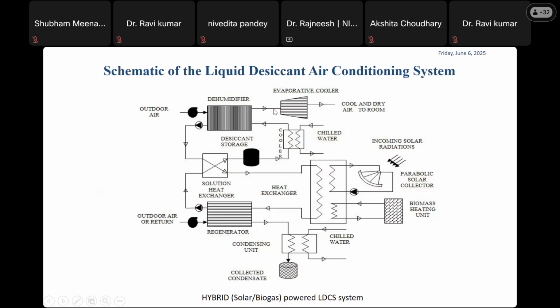And as we discussed with the help of psychrometry, the moisture content is also to be increased a little bit up to the comfort conditions. So it has to be passed through an evaporative cooler, and we get the desired output. But the additional setup, this whole complicated arrangement, is provided to run the system continuously. That is why we have provided the desiccant storage. There is a solution heat exchanger. Then this is the regenerator, where the desiccant material that has passed through the dehumidifier will be stored and then passed through the regenerator as per the availability of heat energy.